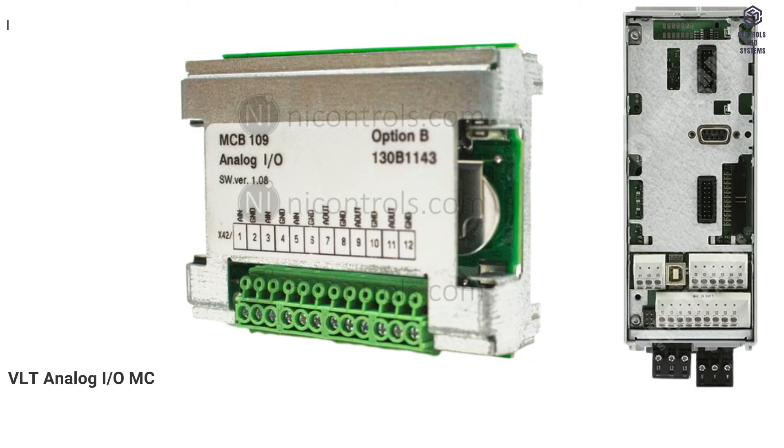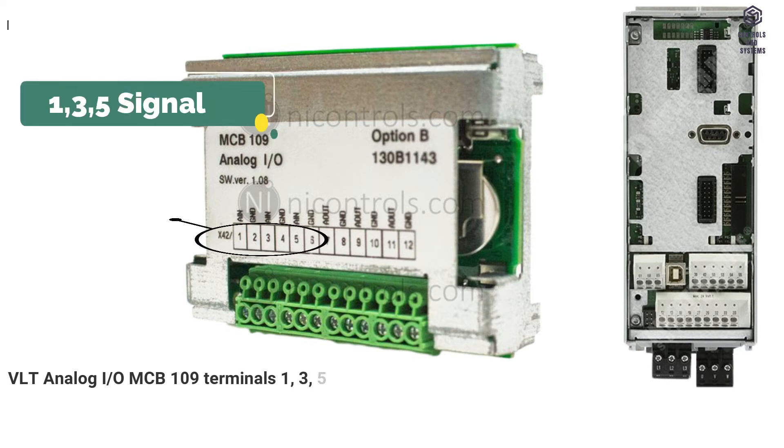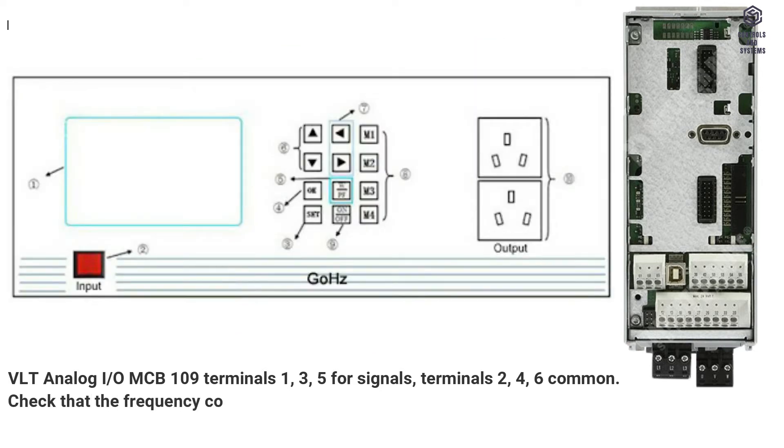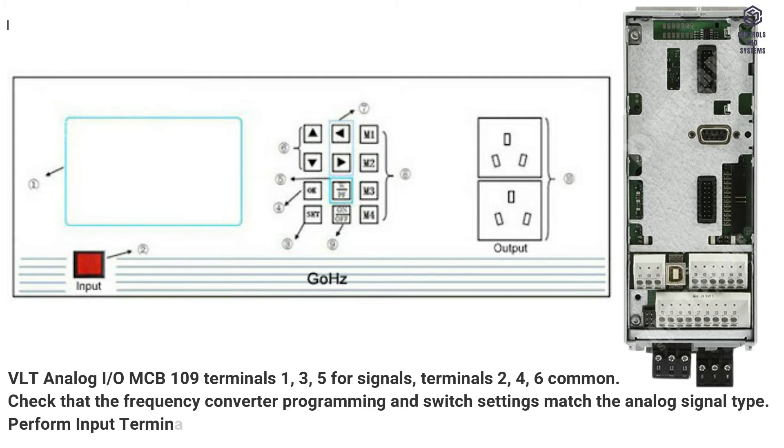VLT analog I/O MCB 109 terminals 1, 3, 5 for signals, terminals 2, 4, 6 common. Check that the frequency converter programming and switch settings match the analog signal type. Perform input terminal signal test.